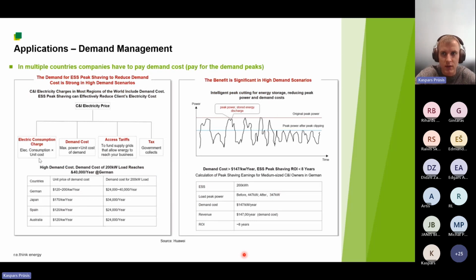The next application that's probably not so important for us is demand management. So for example, in different European and other countries, you have an additional demand cost for power requirements that exceed certain limits. And you can use these solutions just to do demand shifting, which means that you can add these batteries and charge them from the grid. And when you need this high output power that you would, in other cases, have to pay demand increase costs for, you would use energy from the grid and from the battery, thus avoiding these demand charges.